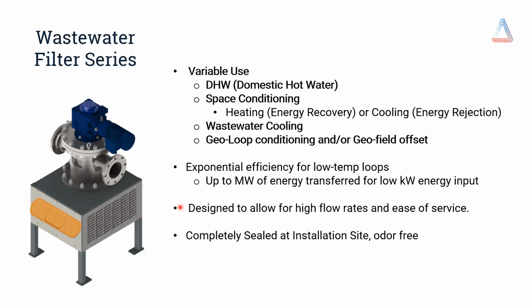So with this, I like to refer to the wastewater filter type of system as being exponentially efficient by transferring energy into these low temp style or ambient temp style loops. And this is because, as you saw on the previous slide, we can transfer up to megawatts of thermal energy for very, very low kilowatt energy input. Usually only a couple of small scale motors are used to operate the equipment, provide that filtration, and see that very, very large scale thermal transfer into your systems.